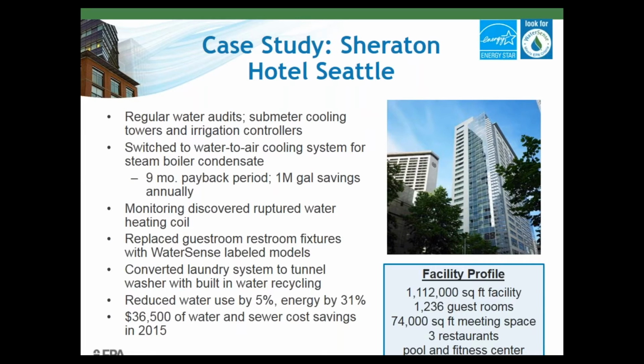One of the things they did was start regular water audits and sub-metering their cooling towers, irrigation systems, and irrigation controllers. They were able to switch to water-to-air cooling systems for their steam boiler condensate, which saved about 1 million gallons of water per year, with a pretty quick payback period. It was a really significant reduction achieved quickly.